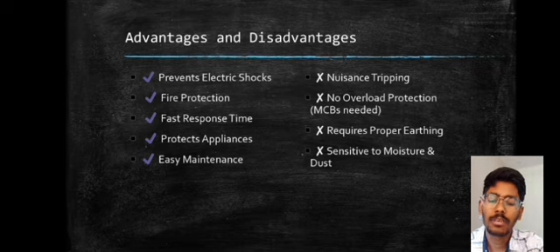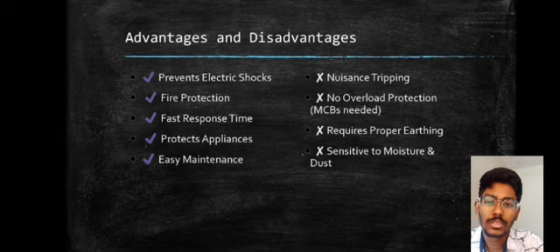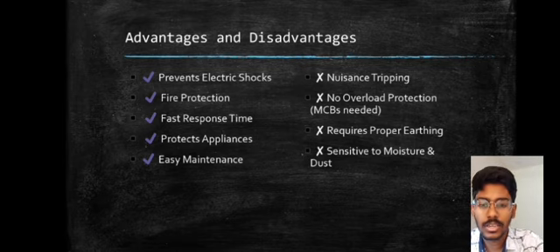The disadvantages of ELCB are as follows. They may trip unnecessarily due to minor leakage. They do not protect against overloads or short circuits. For that, we need an MCB or an MCCB. Another disadvantage is they require proper earthing to function correctly. Moisture and dust can affect their performance.